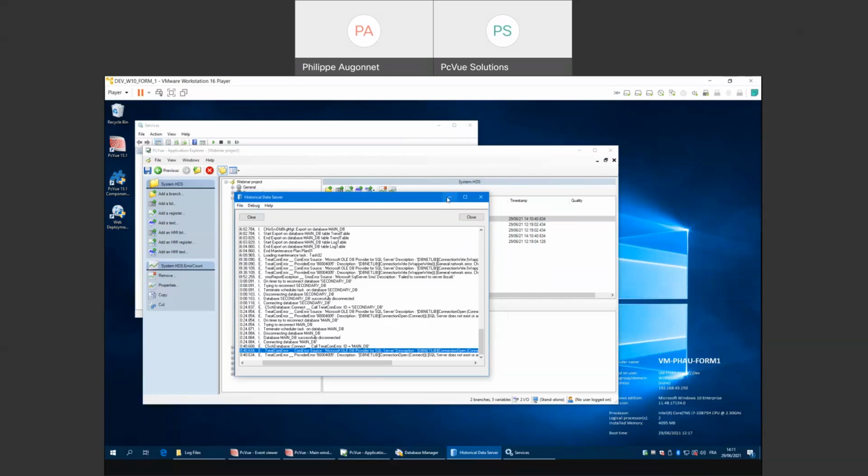So from then, I can have a look at the trace and investigate what the problem is between the HDS and the database system. If it's a remote database, that might be due to a loss of connection on the network between the two. So look for errors regarding the network, router, whichever cause can be provoking the loss of connection between my SQL Server and my HDS machine.